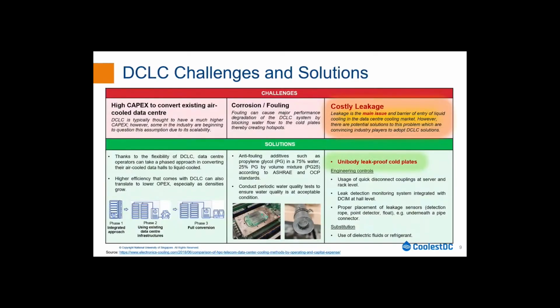But one of the other issues preventing liquid cooling from being deployed widely is the leakage concern. With air cooling, there's less concern of leakage - if some air leaks out from the rack, it's not going to pose any serious issue. But if you pump liquid into your IT cabinets, into your IT racks, into the server, if there's a leakage, that can potentially damage your costly IT equipment. So the ability to address the leakage risk is paramount in helping push for wide adoption of liquid cooling.